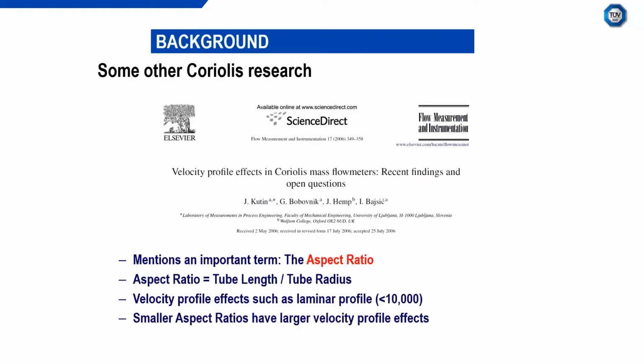This paper basically states that there are velocity profile effects in the laminar profile regime. That's below a Reynolds number of typically 10,000, although it does vary with entry lengths. People define laminar flow below, say, 2,000, 2,300. A lot of papers show that you can get laminar effects depending on your entry lengths all the way up to 100,000 Reynolds number. It really just depends on how much installation you have, upstream straight pipe work. What we find for this paper is smaller aspect ratios have larger velocity profile effects. So what that really means is smaller aspect ratios have larger deviations due to Reynolds number, so velocity profile / Reynolds number effects. That's what that paper stated, and that was back in 2006.